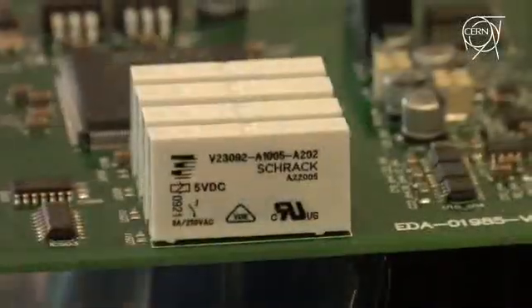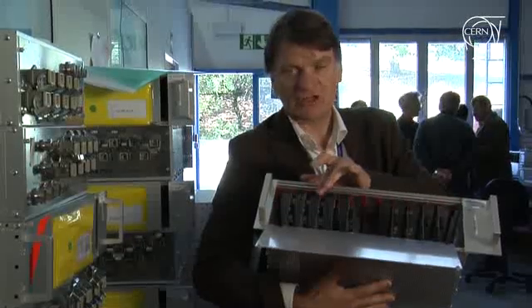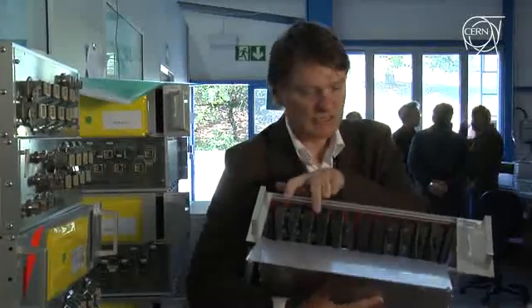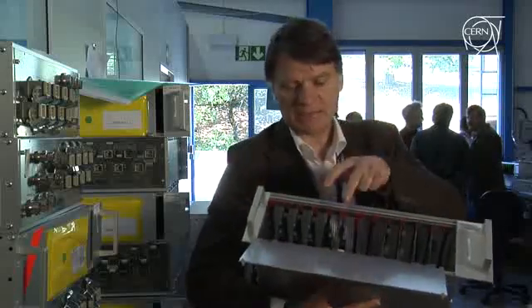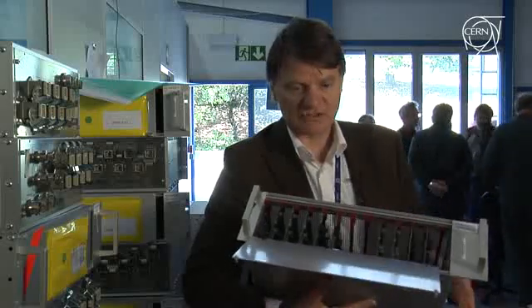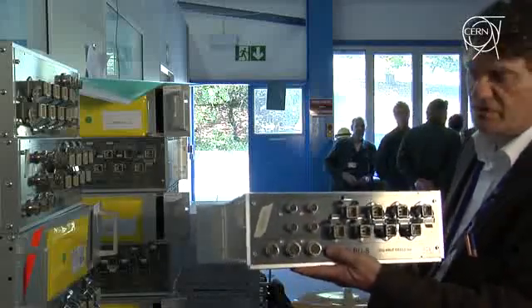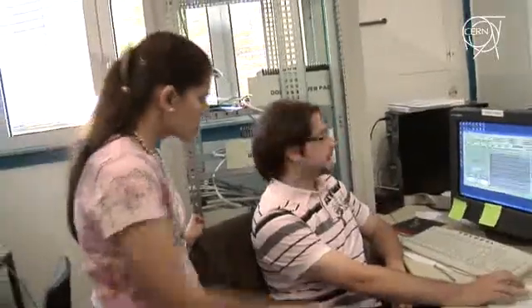It contains a number of boards of two types: one for the distributed busbar supervision and protection — these three and these two that you see here — and the other type is these boards, which are for symmetric quench detection. We produce the whole chassis, which you see the backside here, with the connections to the magnet, to the interlocks, and to the firing systems, which will fire the heaters from this unit.